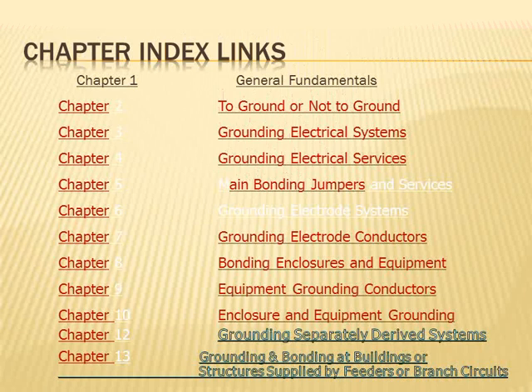System number 2 is the ungrounded system. You have heard about ungrounded systems. You typically have it as a delta, could be a Y. So your power system is in no shape or form referenced to the ground. For people who don't understand the ungrounded system, imagine a 9-volt battery, and you take the positive and negative and put them across a light rated for 9 volts. The light will go on. That battery is not grounded in any way, shape, or form. You take the negative and tie it to the ground, a water pipe or something, and now you have grounded that 9-volt battery. That's what a grounded system versus an ungrounded system is.